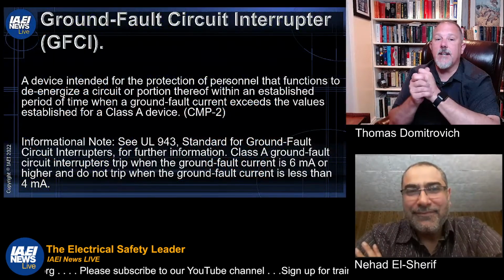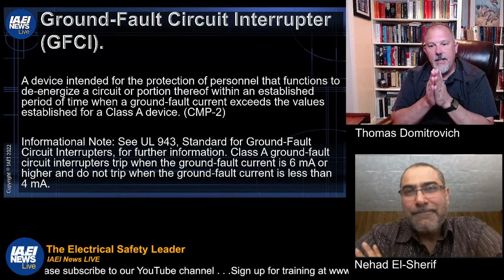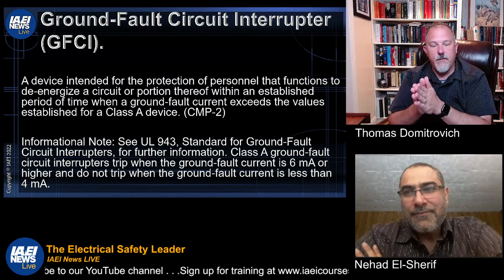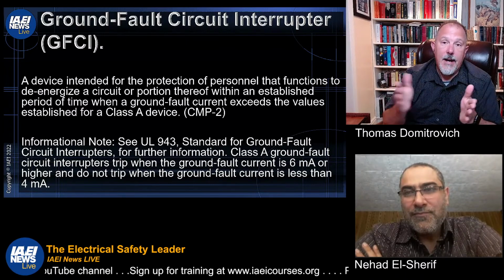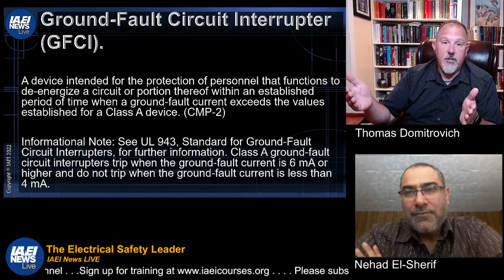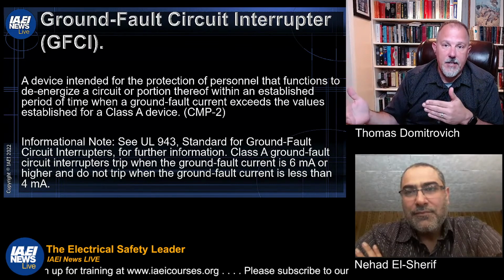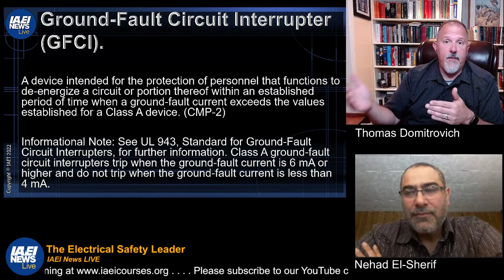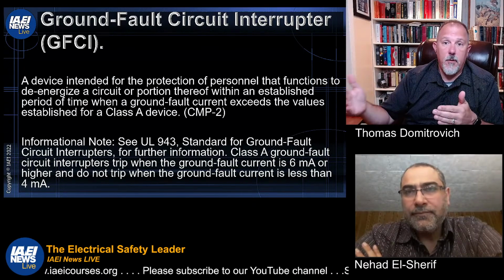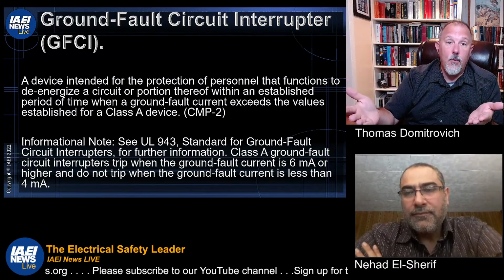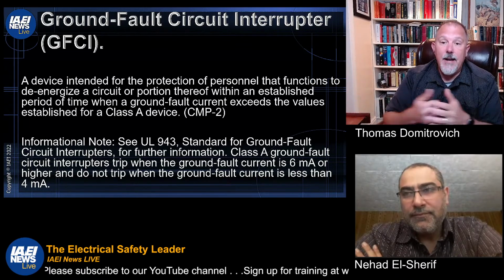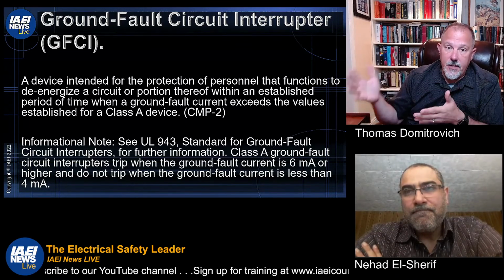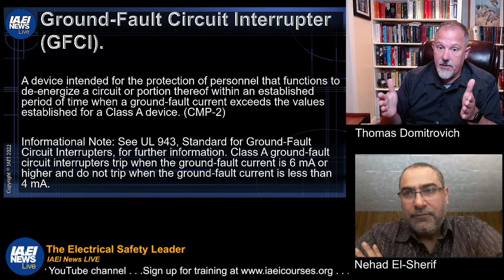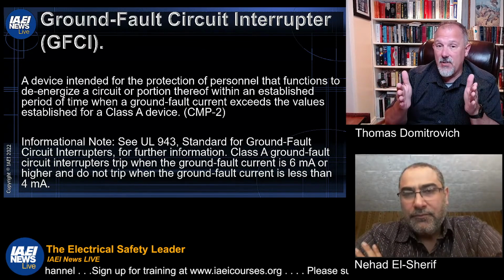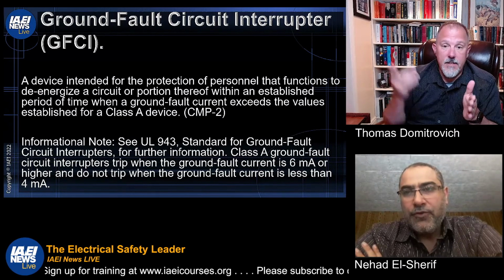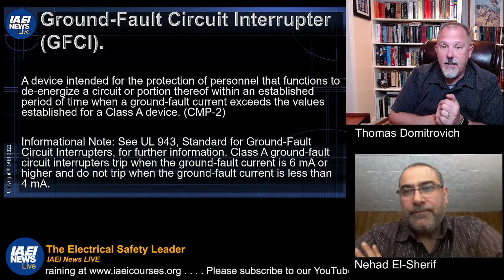So let's first talk about the definition of a GFCI. Nehad, I know this can be confusing for some people. In fact, I sometimes have a hard time with some individuals. They'll just say, I need GFI protection, and you don't know if they're talking ground fault circuit interrupters or ground fault protection of equipment. And now we've got a special purpose GFCI. So I think covering the definition of what a GFCI is and establishing that as a baseline is probably a good thing. So this is the definition out of the NEC.